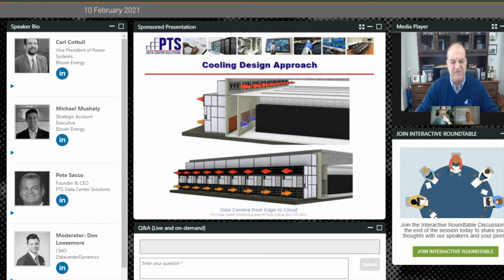So what you're looking at, everywhere you see a red arrow and an orange arrow, that is a singular 250-kilowatt cooling module, scalable in different sizes, and that's all you need. By the way, you'll notice it's sitting outside the building, which is both good and bad. It makes it very hard to use in a retrofit situation, very easy to use in a greenfield situation. And what you're looking at there, I think there's 11 of those—that would be 10 times 250 is 2.5 megawatts, plus one.